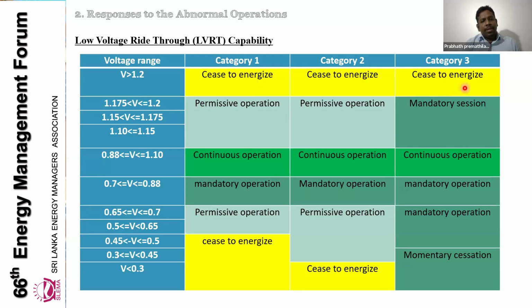Cease to energize mode means that synchronization with the local electrical power system is maintained, but it will not inject any power into the network. Once the system has recovered, it can inject power, maybe 80%, maybe 90%, or some significant portion of the power generated before the event. That's what we call cease to energize. And permissive operation is another operation mode. In permissive operation mode as well, it will maintain synchronization with the network. But as per the utility requirement, it can inject power or it can cease to energize. That's the utility's decision.